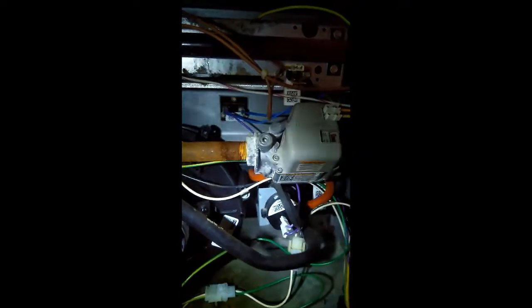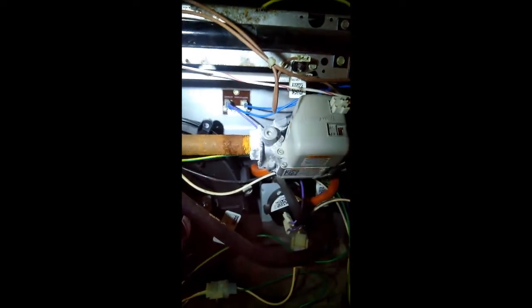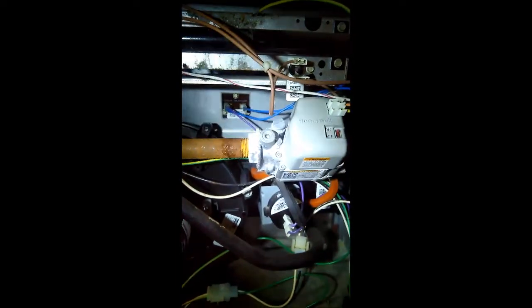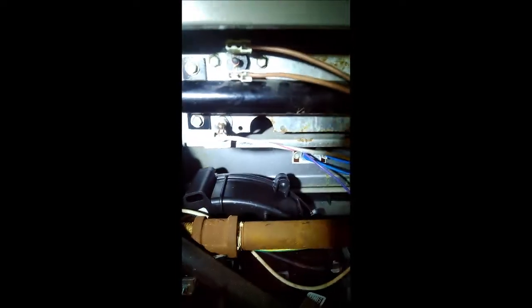So it basically contributes to some computer logic that gives you binary zeros and ones, and the computer does a conditional if statement kind of thing where it says, okay, if there's no flame and there's a good vacuum on the inducer fan assembly, blah blah blah, then you can turn the furnace on, and if not, then it thinks there's something wrong and doesn't turn it on. Basically, these are supposed to be closed to indicate a closed circuit, otherwise the furnace won't turn on.